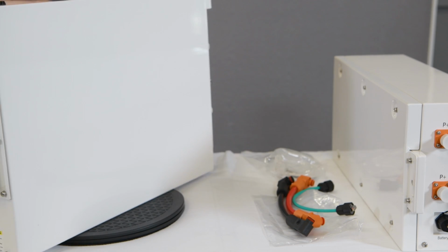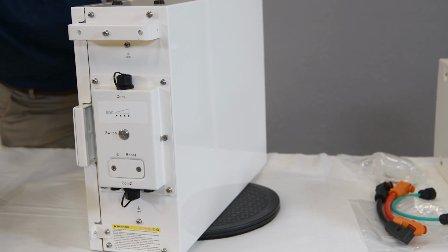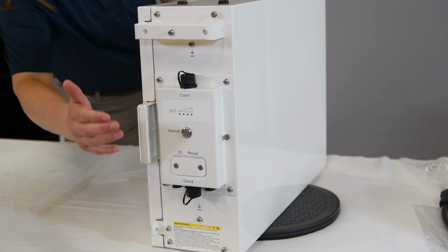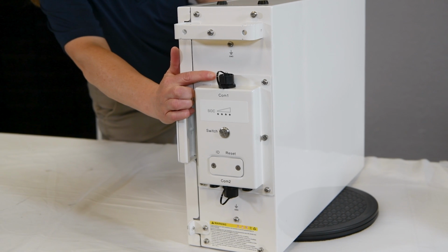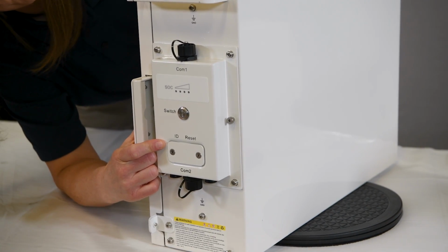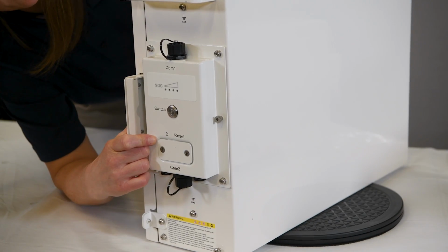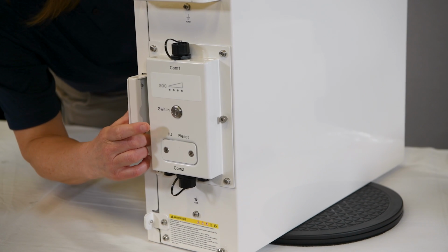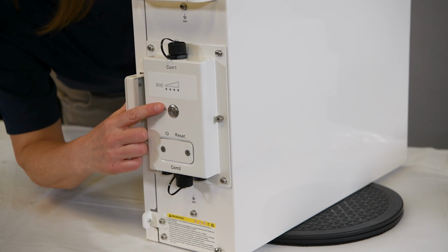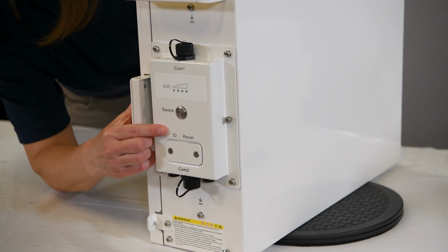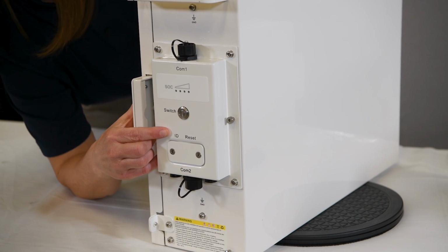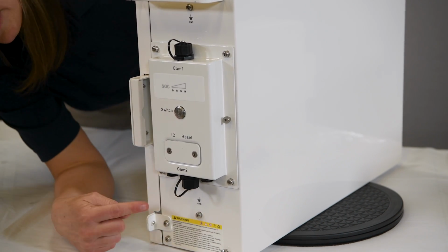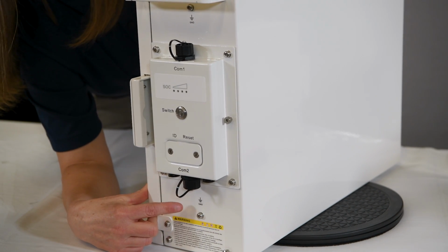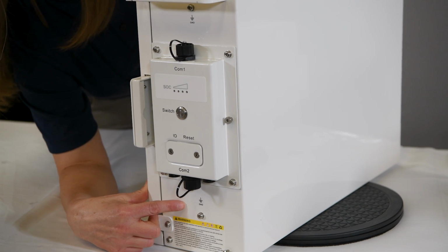On the opposite side, you'll find the communication ports with the input, again located at the bottom, and the output located at the top. Just above these, there's a ground screw and the LED state of charge indicator for easy monitoring. Below that is the power button. And if you unscrew this area, you'll uncover the ID switches essential for configuration. Additionally, there's another ground screw at the bottom side for extra grounding options.